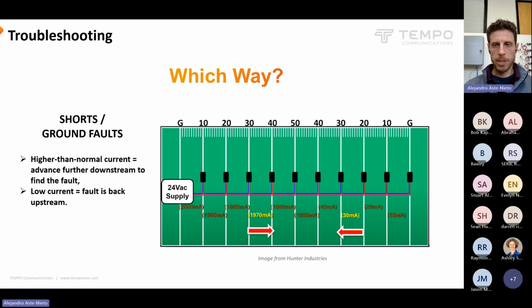In terms of narrowing down where problems are, if we have high current coming from the controller onto a wire path, then we're going to look for where that high number drops away. If we take another measurement here and it's still high, we know that our problem is still downstream. If we take a measurement here and it's a lower number, we know our problem is upstream. So just keep that in mind. If you have a high number, the problem is downstream. If your number is not high or it's low, your problem is upstream.